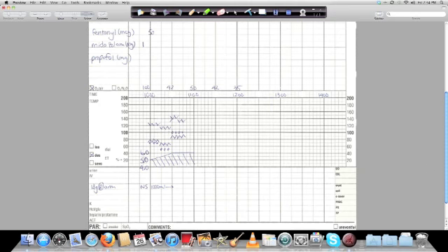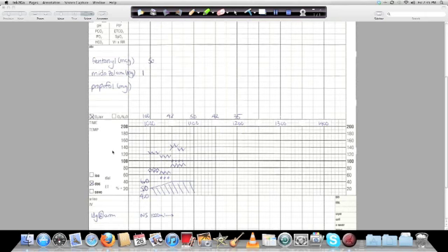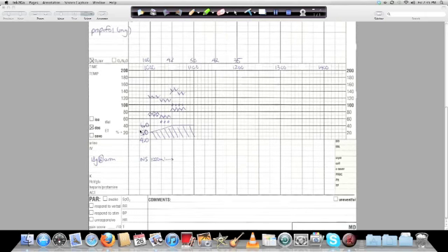And on the bottom of this area here is how we actually track the maintenance of the anesthesia. So most operations will use desflurane to maintain the anesthesia, desflurane vapor, which comes in through the circuit, and you want to track the expiratory concentration.